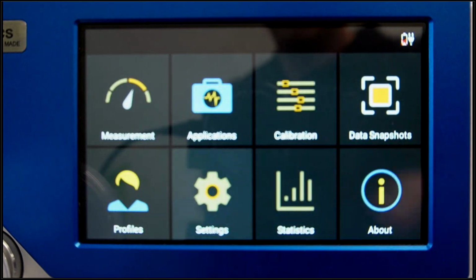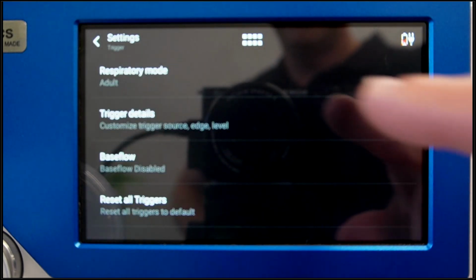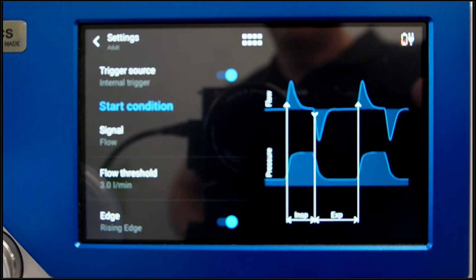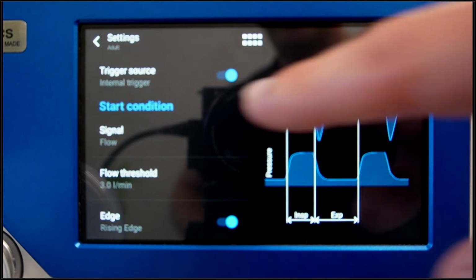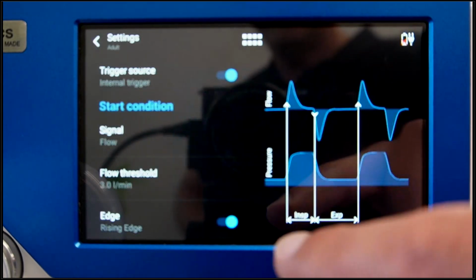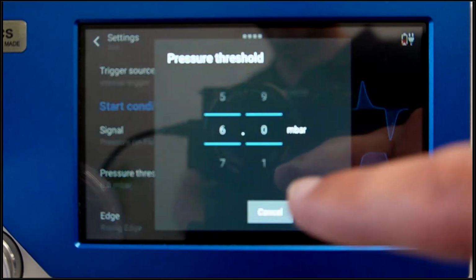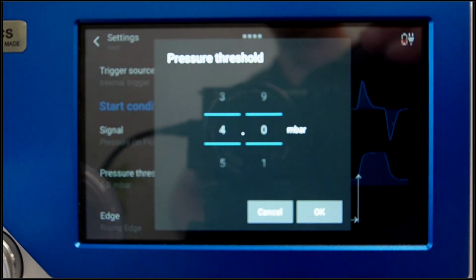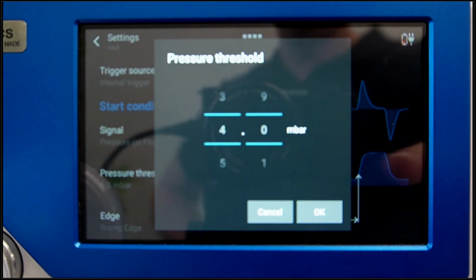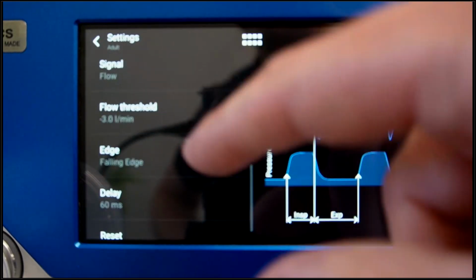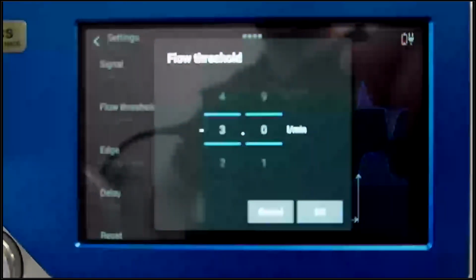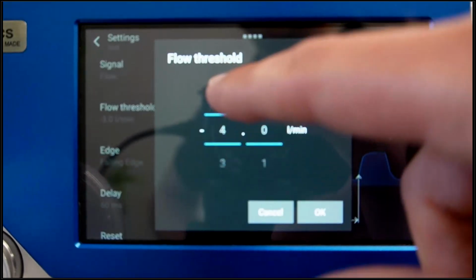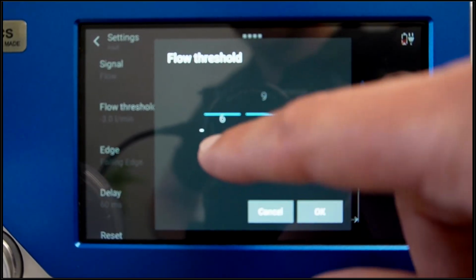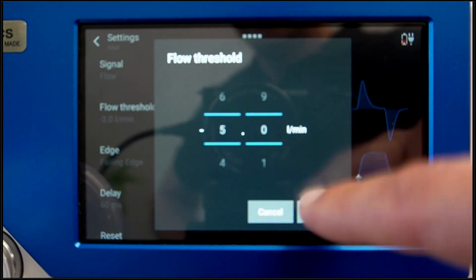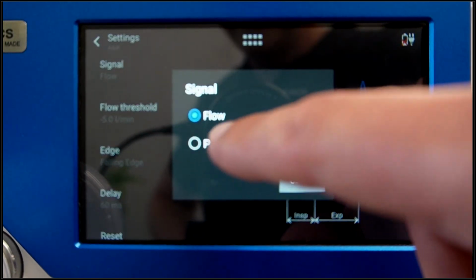So on this analyzer, in the settings, I can go into the trigger settings, and I will tell the device now that I want to switch from my flow waveform to my pressure waveform. And I'm going to set the level for the start trigger to EPAP plus 1. EPAP is 3, so I'm going to set it to 4 on a rising edge, and I'm going to set my stop or end trigger to IPAP minus 1. IPAP is 6, so I'm going to set it to 5, and also pressure.